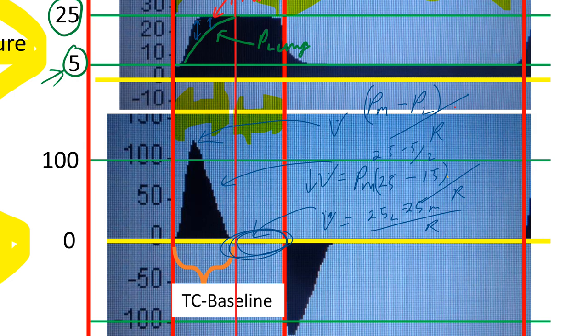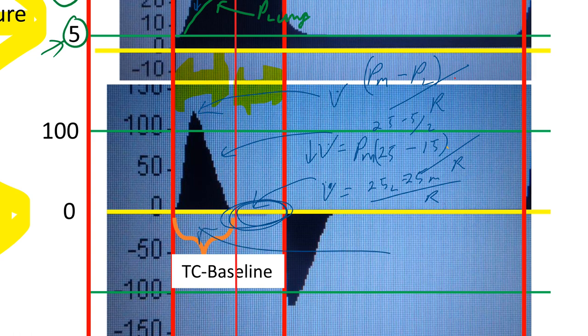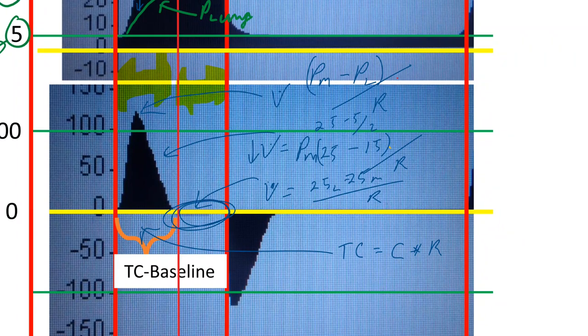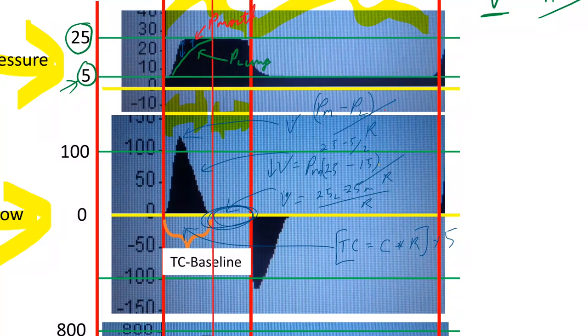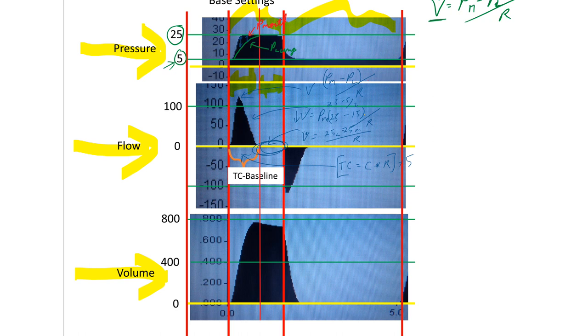The concept of how long this filling takes is called the time constant, and we know that time constant equals compliance times resistance. It takes about five time constants to achieve total filling — that is, equilibrium between mouth pressures and lung pressures. With our present settings — pressure of 25 and baseline of 5 — we have a pressure gradient of 20, resulting in our inspiratory flow and a tidal volume delivery of about 800 mL.